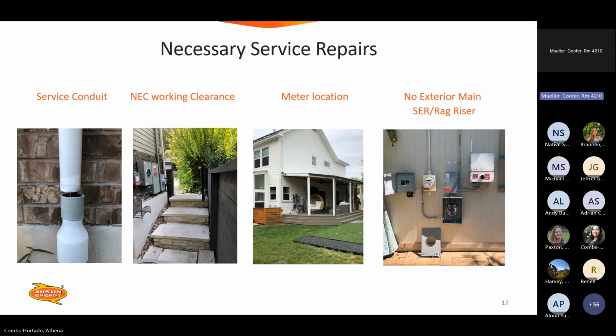So some key examples here of necessary service repairs. Left to right is service conduit, so that's an underground service lateral, right? I find it most commonly on the east side where the earth tends to settle. So if something like that happens, you've got exposed service conductors right there, which will need to be repaired under a repair permit, because you'll be working on the, should that be an upgrade permit? I believe that's a repair permit because you're working on the line side of the revenue meter. So pay close attention at site assessments, because that's something that easily gets missed.